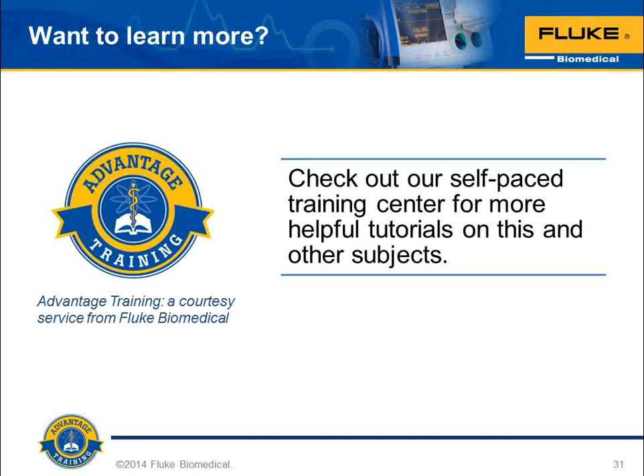There's not supposed to be, but for example, two weeks ago I brought this very presentation to the Third Biomedical Association Conference in Bogota, Colombia, because the government there is trying to change the requirements around calibration of certain medical device categories. Unfortunately, the ones they're talking about are things like defibrillators, infusion pumps, ventilators, things that we have seen and have evidence of incidents that show that the medical devices, even if they are maintained, if we're not doing the proper testing, we're not finding the problems before they happen.